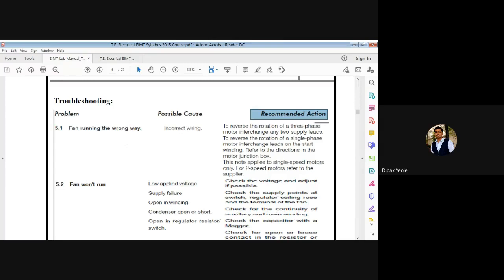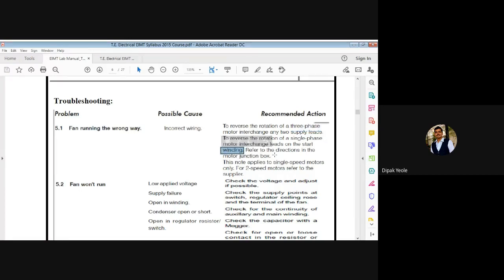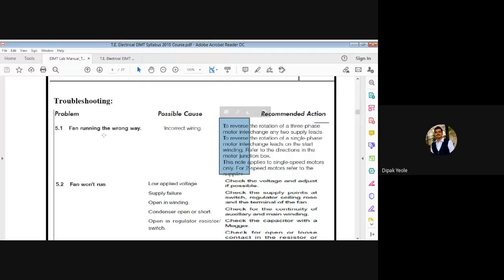The possible cause is incorrect wiring. To reverse the rotation of a three-phase motor, interchange any two supply leads. To reverse the rotation of a single phase motor, interchange the leads on the start winding. Refer to the direction markings in the motor junction box. This note applies to single speed motors only; for two speed motors, refer to the supplier. This is the recommended action to remove this problem.